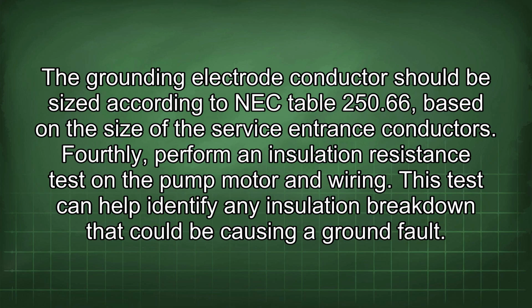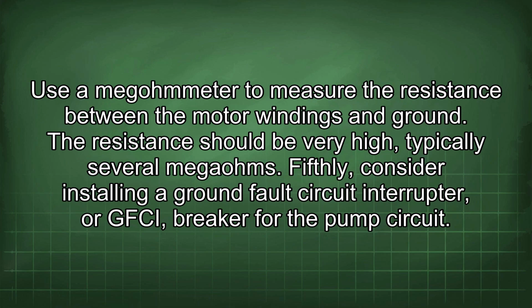Fourthly, perform an insulation resistance test on the pump motor and wiring. This test can help identify any insulation breakdown that could be causing a ground fault. Use a megohmmeter to measure the resistance between the motor windings and ground. The resistance should be very high, typically several megohms.